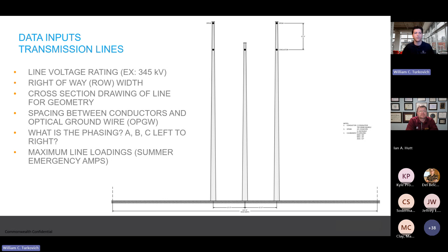Some other data inputs are the number of conductors per bundle. As an example on the right, we have a dual conductor 795 Drake. The conductor size is also important - the geometry of these cables has a big impact on what the EMF will determine. The optical ground wire protects the transmission lines from lightning strikes and can provide a communication path if designed that way. And then one of the more important data points we need is the minimum height off the ground.